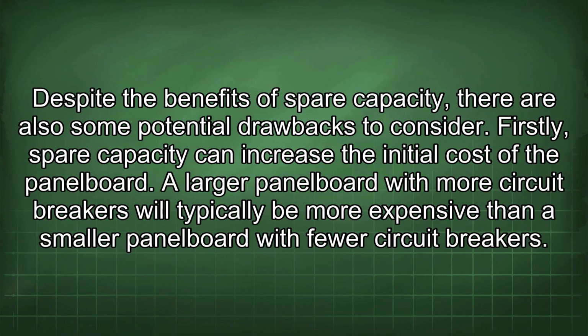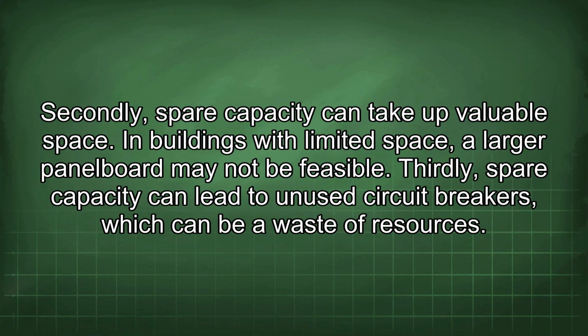Despite the benefits of spare capacity, there are also some potential drawbacks to consider. Firstly, spare capacity can increase the initial cost of the panel board. A larger panel board with more circuit breakers will typically be more expensive than a smaller panel board with fewer circuit breakers. Secondly, spare capacity can take up valuable space. In buildings with limited space, a larger panel board may not be feasible. Thirdly, spare capacity can lead to unused circuit breakers, which can be a waste of resources.